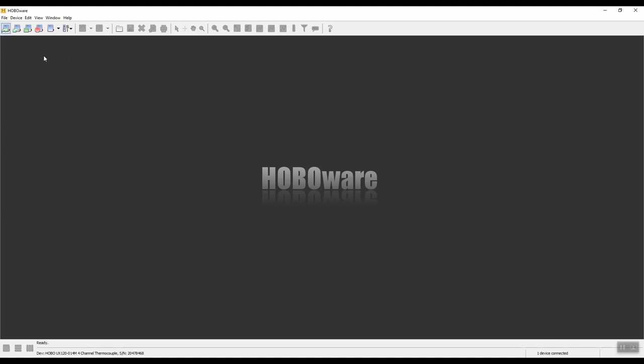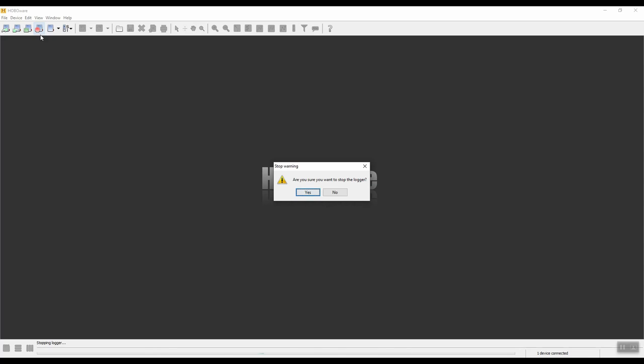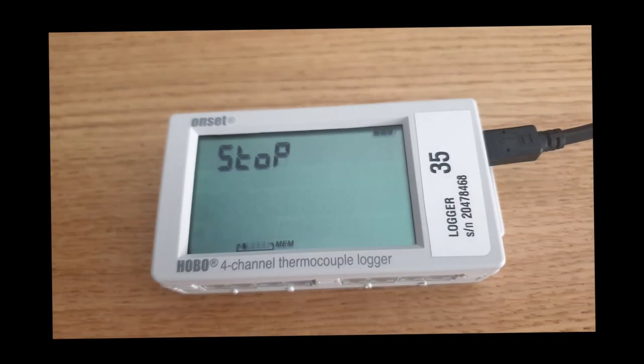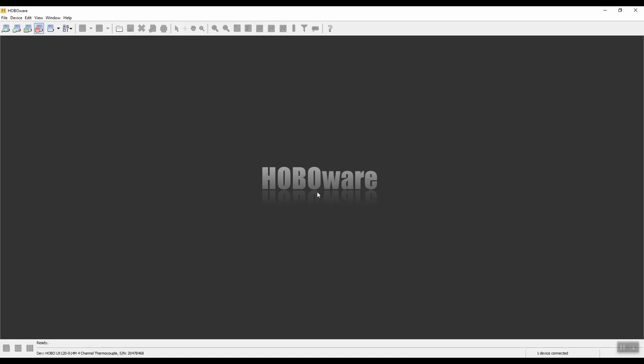The next thing I want to show you is if you want to, for example, stop the data logger from running, you don't want to use it anymore, just click on the button, the stop device. This will stop the logger from logging. Click on yes when the window pops up. The display on the Hobo logger will say stop. Click on OK. We can disconnect the Hobo logger from the PC. We can do this if you wanted to conserve some battery and you're not using your logger.